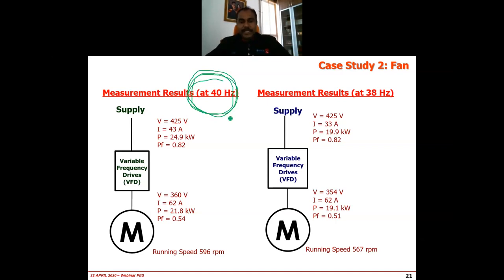So what we did was, we did some study. I said, okay, let's do a study. We hooked up our power measurement meter before the variable speed drive, and also after. So you will notice a few things here. Number one, when it is running at 40 hertz, in fact, we tried to push to 50 hertz, we noticed the power is less than 30 kilowatt when it is running at 50 hertz. But the motor is a 120 kilowatt motor. That's huge. That means, as I told you just now, this motor is actually driving about 30% loading. That means it's running at a very low efficiency all the time. 120 kilowatt motor is taking only about 30 kilowatt when it's running at 50 hertz.